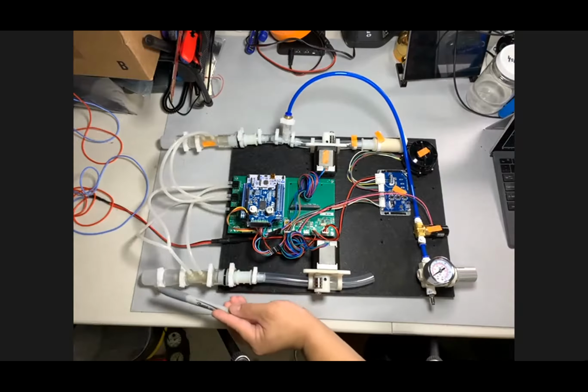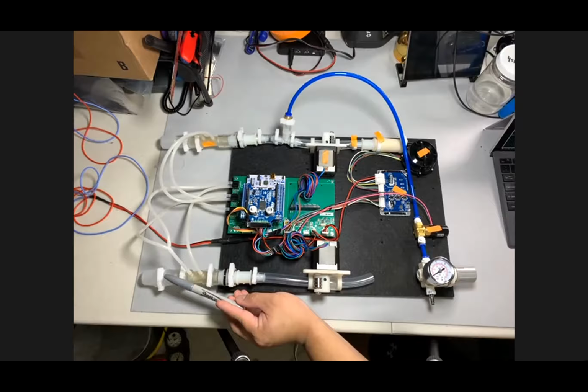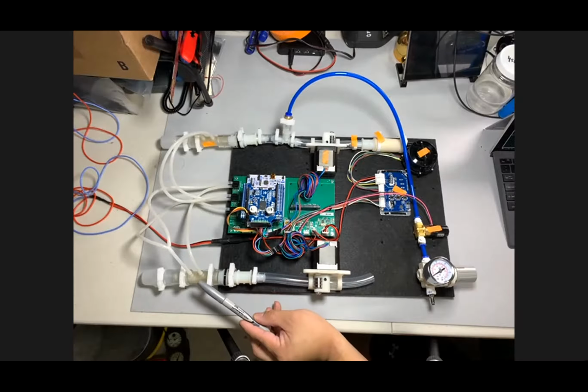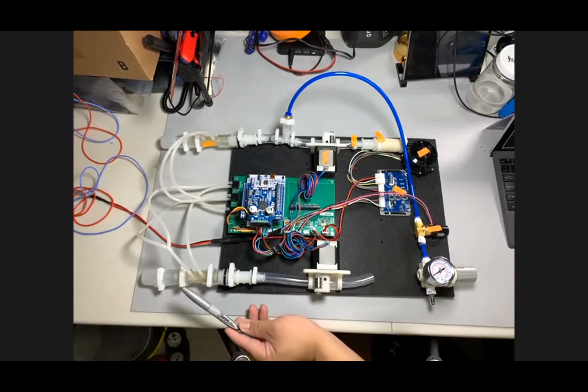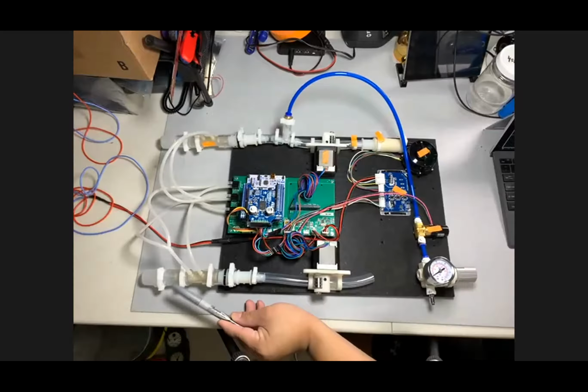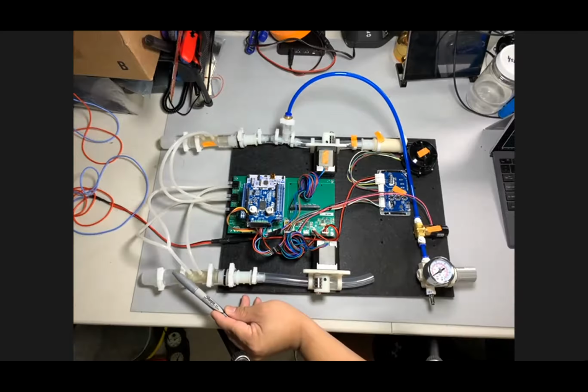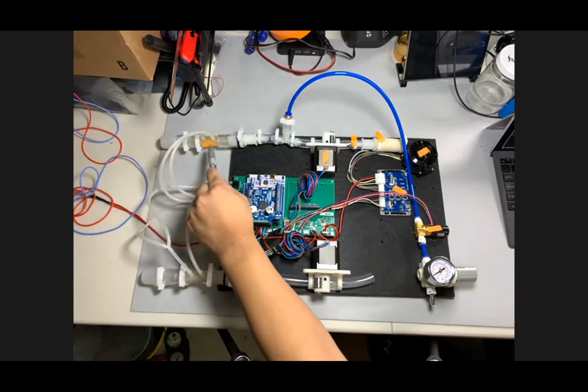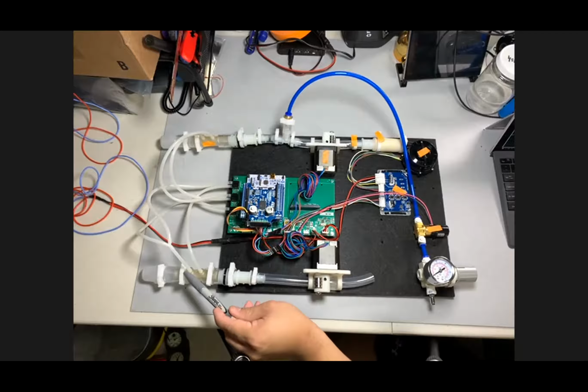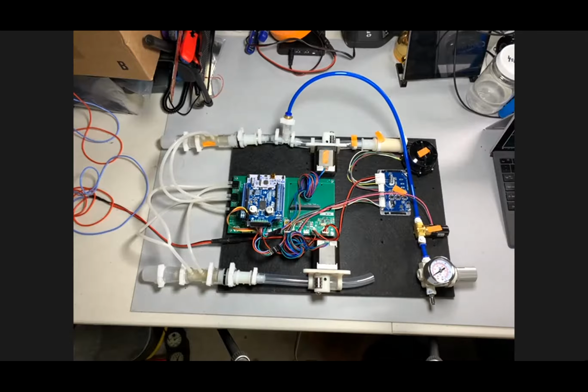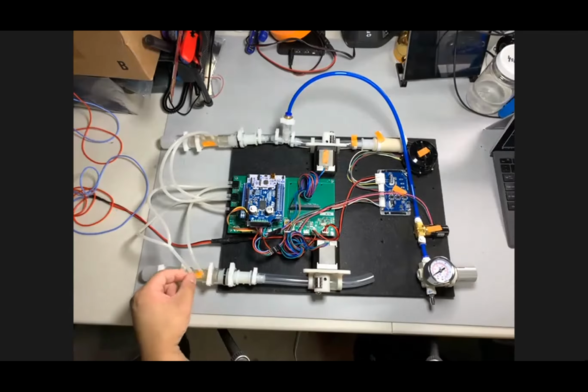You get the reverse of that here on the exhale side, in that the venturi, the vacuum port, is now on this side, which is on the ventilator side, and the reference pressure sensing is on the patient side. And because the reference pressure sensing is on the patient side, this is the more accurate place to tap off the patient pressure. Now, we could just put another port here, right? That would do the same thing, or we could put a port here. But if we're going to use one of the existing ports in the venturi, this is really the only one that we can use. I'll go ahead and mark this venturi also as being locked in the design for now.